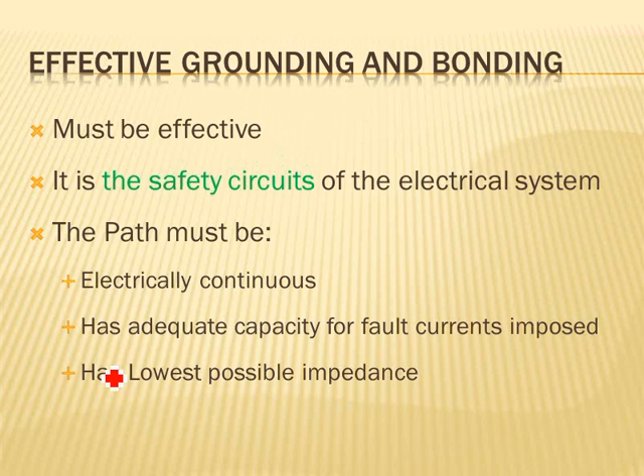Right? How many of us stand there and try to move it away and tie it with a wire nut and accidentally touch the frame? So ground faults account for 85% of your power system faults. The equipment grounding conductor is the safety valve, so it will save you 85% of the time. The ground fault path is your safety net. And what happens to the other 15% of the time?